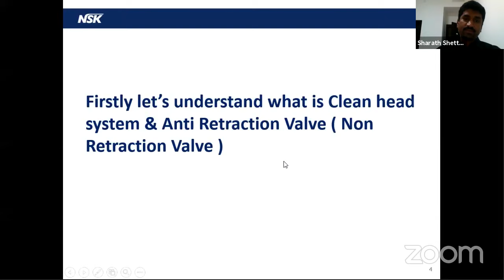In NSK, we have two types of protection in each and every dental handpiece, and those are the clean head system and the non-retraction valve. Let me explain the clean head system. It is a system wherein, during the operation, when you work on the patient's mouth, as soon as you release the foot control, there will be a small amount of negative pressure for a period of hardly 2 or 3 seconds. Every time you release the foot control, there will be a reverse flow. This reverse flow could be the patient's blood, saliva, or debris, whatever is there in the patient's mouth. It tends to suck back, and it goes directly into the handpiece.